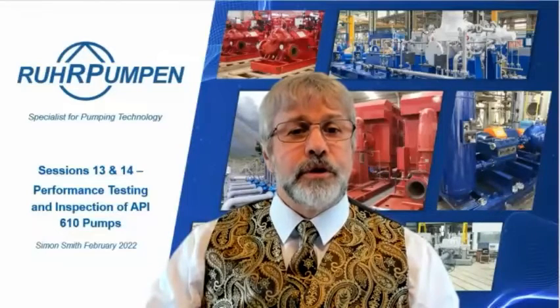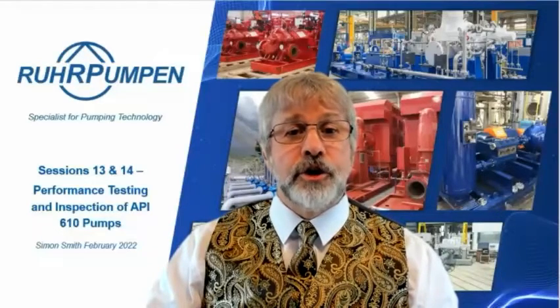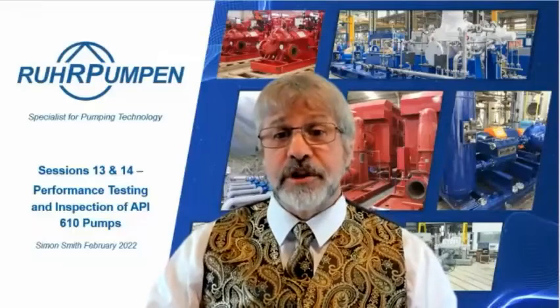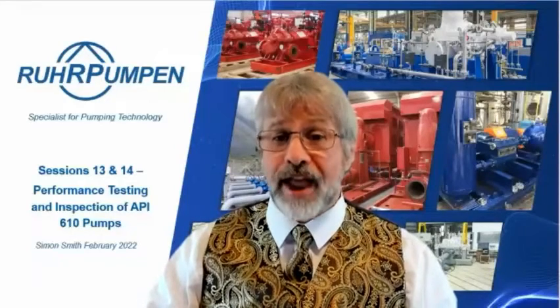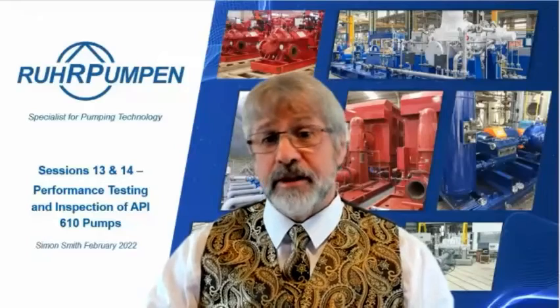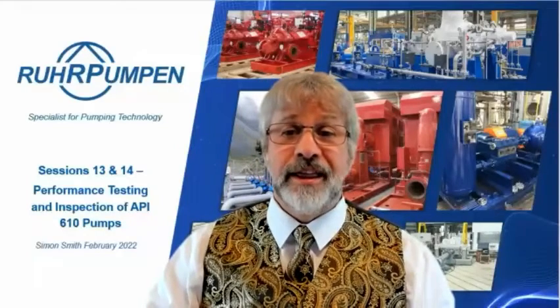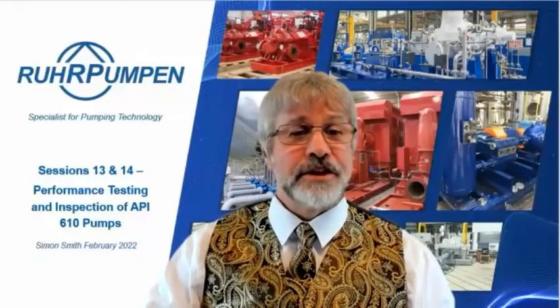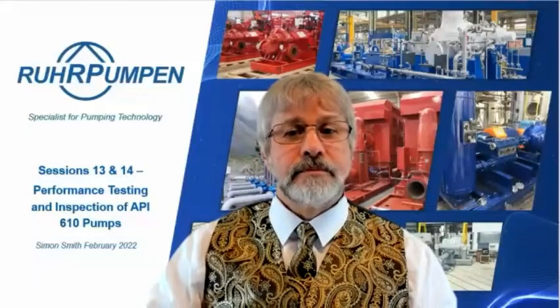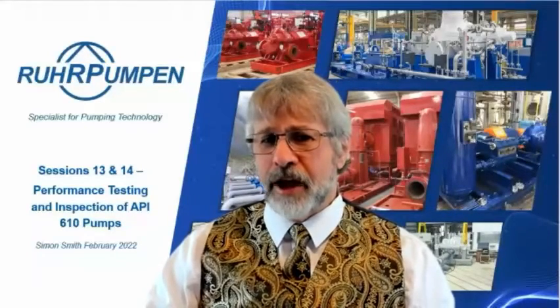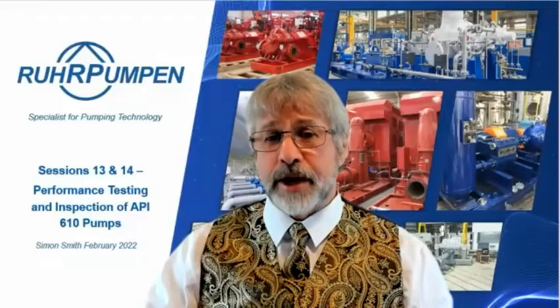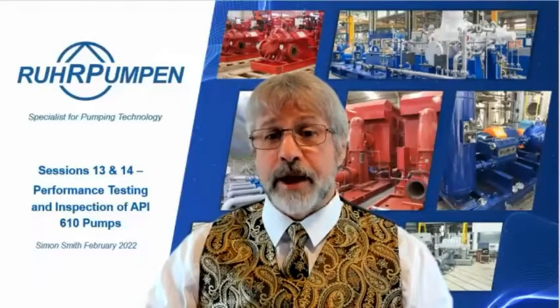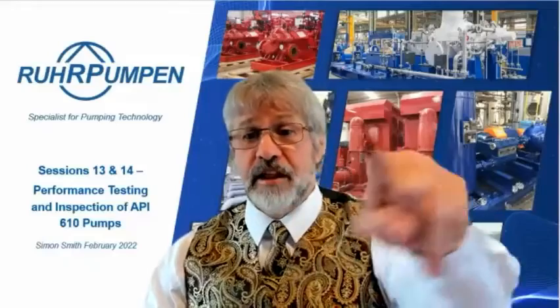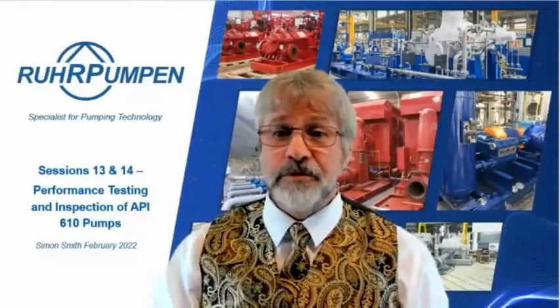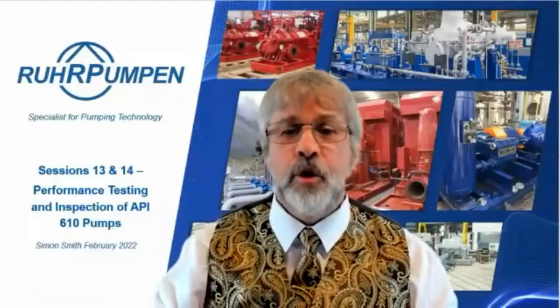Ahmed Metzner says we'd like to know if a PMI test is an optional test or not. Yep, it's an optional test. If you specify what you want to have PMI tested, then the pump vendor can analyze it and tell you how much that's going to cost you. Generally, it won't be too bad. I mean, I've seen it done during a final inspection. A third-party inspector has said, can you please test it here and here and here? So a PMI machine, ping, ping, ping, quick and easy.